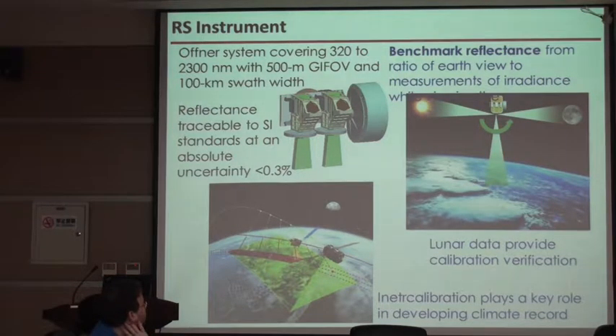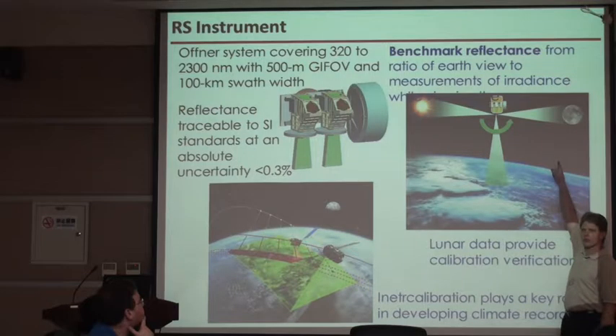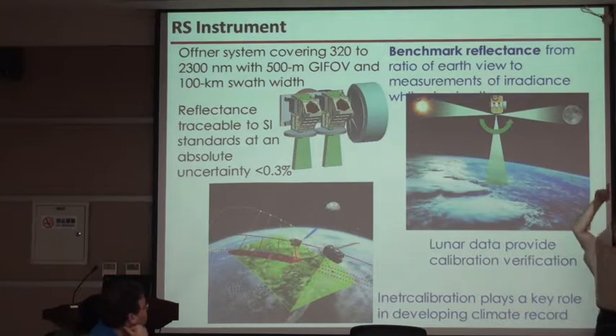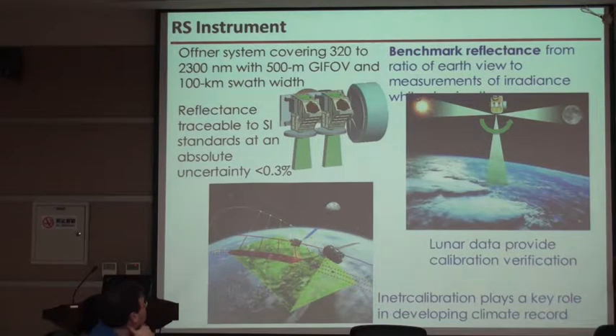The problem is, because we have a 50,000 time difference between the Earth and the sun, we have to attenuate it in some fashion. And we're using pinholes and neutral density filters. So transmissive filters and pinholes. Those might change. That's where the moon helps. So we use the moon purely as a stability check, not as an absolute calibration. We look at the moon once, and then we look at it again 2 or 3 weeks later, a month later, and we keep doing that.